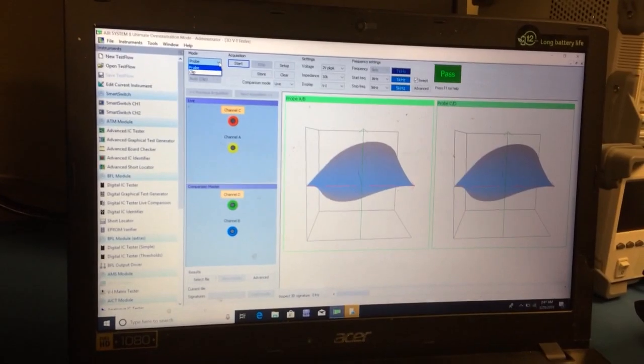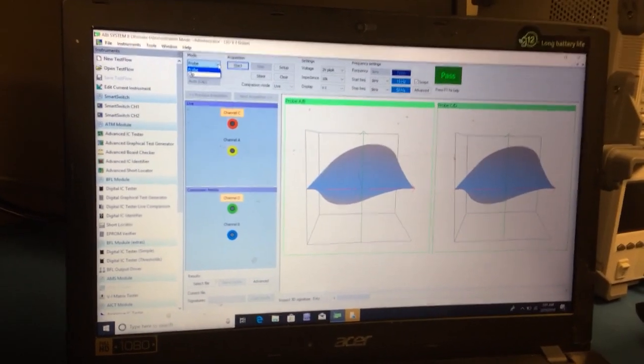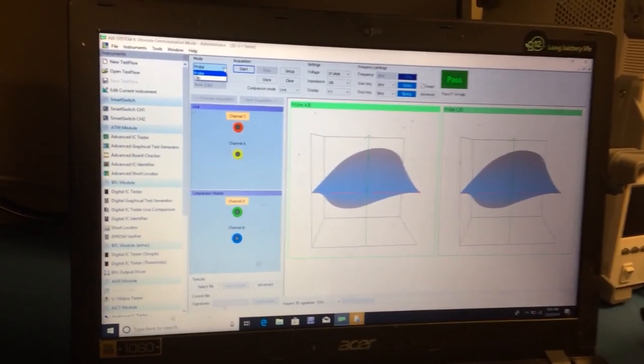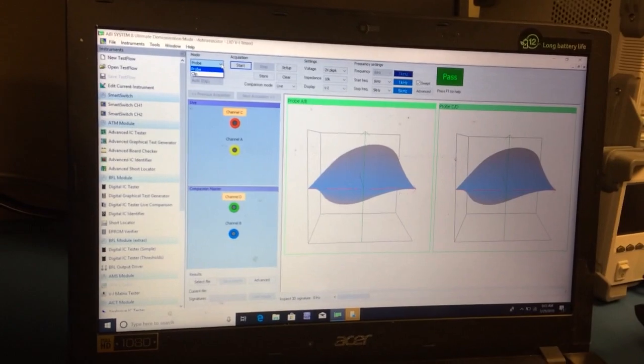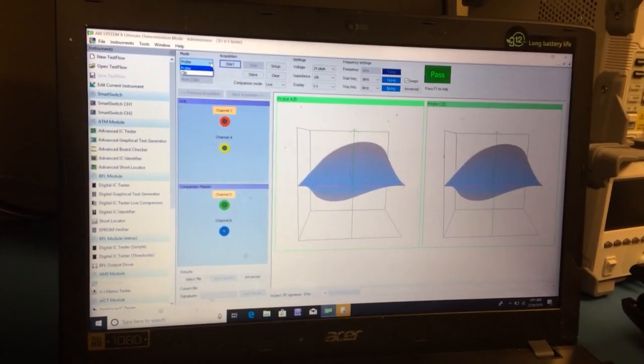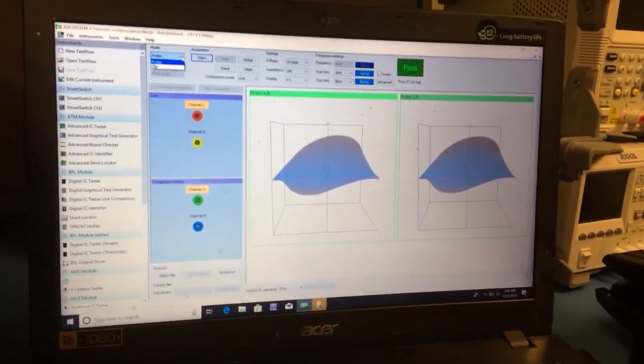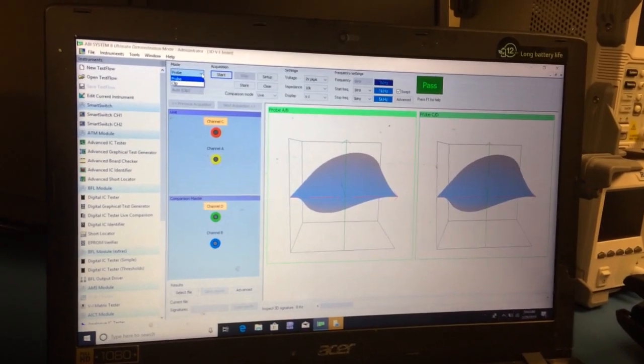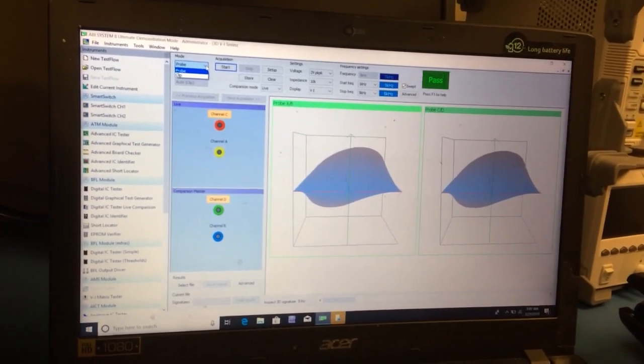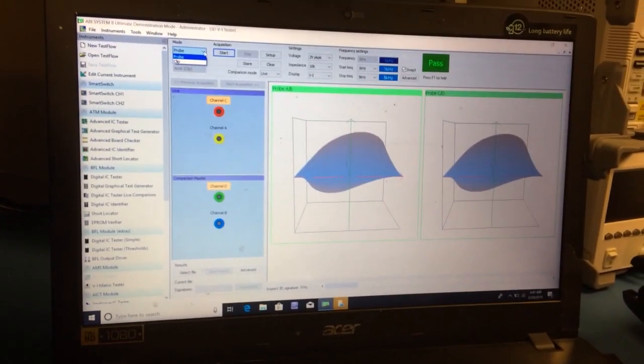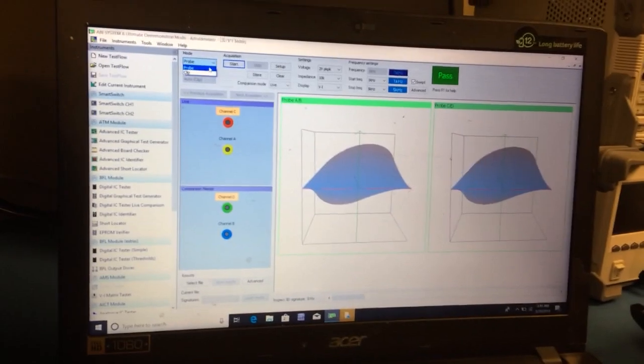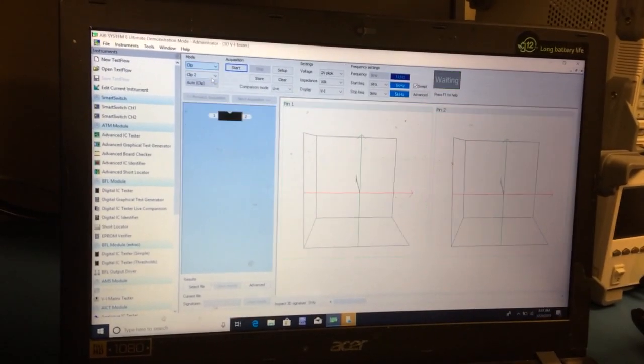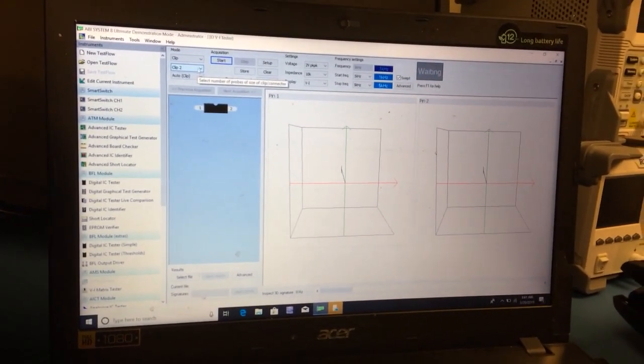...like two different electrical nodes on a circuit board, so we can do node A and node B and we can do a pass failure analysis. What's really cool is we can do a 3D signature analysis and look for deviations within the voltage current signature. We can either do a probe or we can also set this up to do a clip.